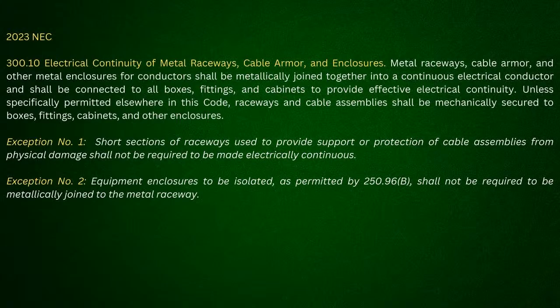Now watch this. Here we go. You've got 300.10. This is where it gets into the electrical continuity of your metal raceways, cable armor, and enclosures. Okay? And it tells you here, in order for this to be installed, your metal raceways, cable armor, and other metal enclosures for conductors shall be metallically joined together into a continuous electrical conductor and shall be connected to all boxes, fittings, and cabinets to provide effective electrical continuity. That's when it becomes a raceway. But in order to get away from this, to show that they'll allow something different, let's look at exception number 1. Oh, I can't believe it. Short sections of raceways used to provide support or protection for cable assemblies from physical damage shall not be required to be made electrically continuous. Why is that? Because it's not a full raceway. It's got to connect from end to end.